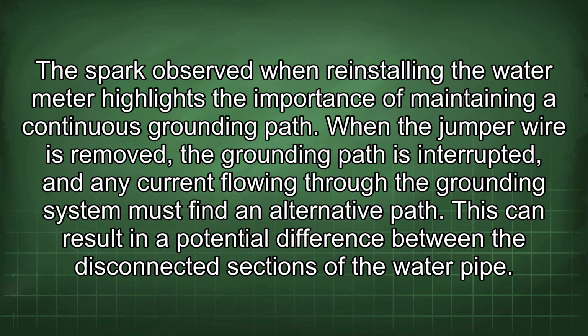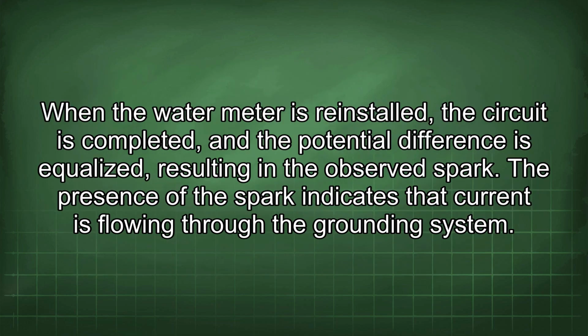The spark observed when reinstalling the water meter highlights the importance of maintaining a continuous grounding path. When the jumper wire is removed, the grounding path is interrupted, and any current flowing through the grounding system must find an alternative path. This can result in a potential difference between the disconnected sections of the water pipe. When the water meter is reinstalled, the circuit is completed, and the potential difference is equalized, resulting in the observed spark. The presence of the spark indicates that current is flowing through the grounding system.